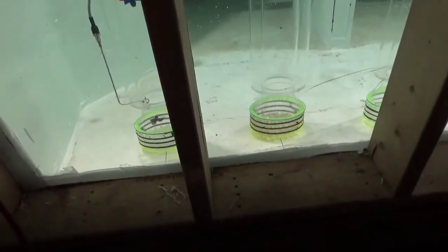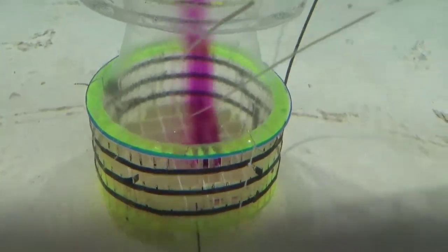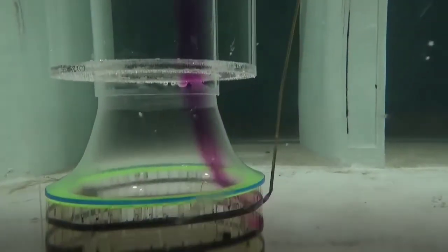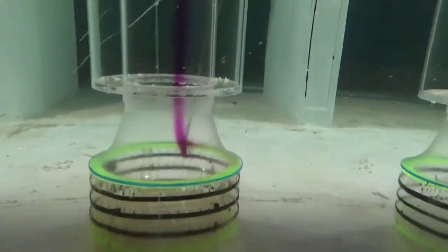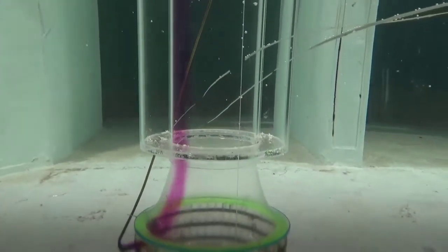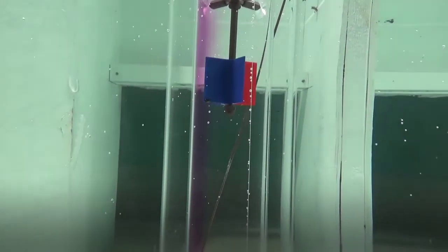Now let's go ahead and take a look at it with the basket in place. You're going to see this flow just perfectly straight up underneath it as it goes up in. There's no rotation to that at all. You can see it on multiple grids. It's perfectly straight. And then up on the side, it stays attached to that throat all the way up in here. As we go around, there's no flow separation at all on that throat. You sit right there, you can see that. And just very, very low, very, very steady rotation.